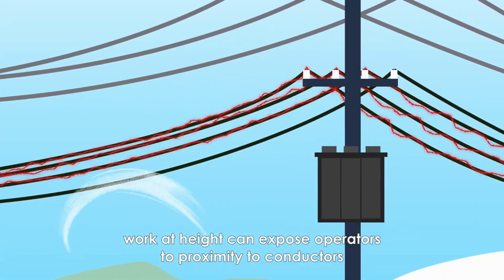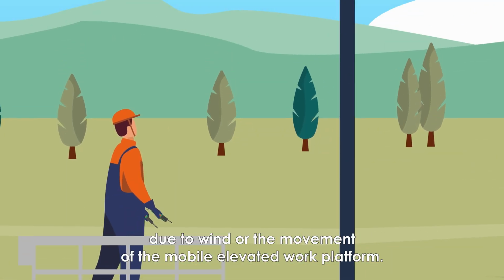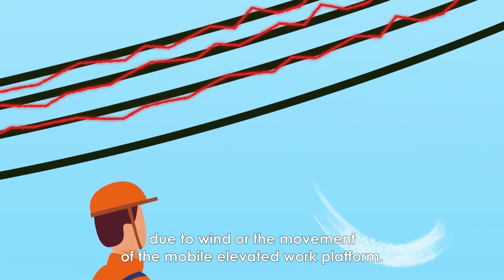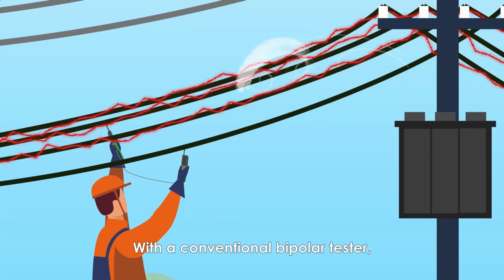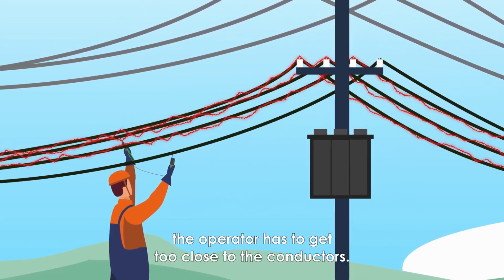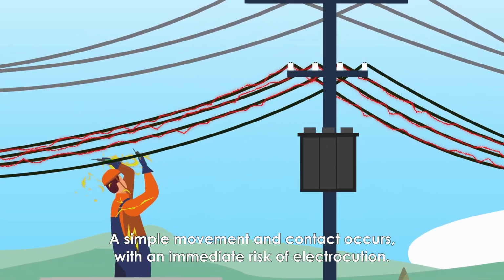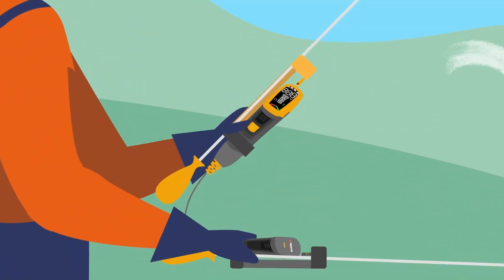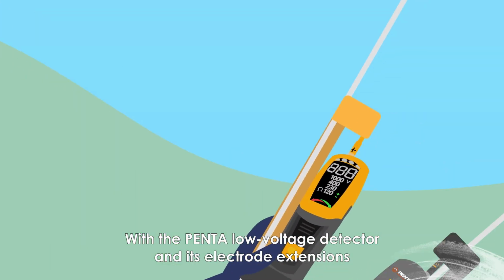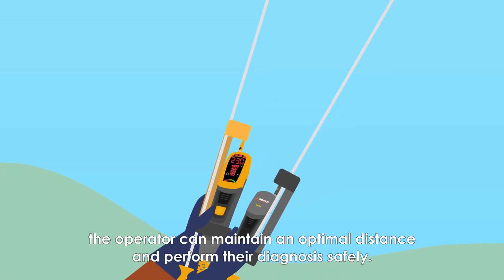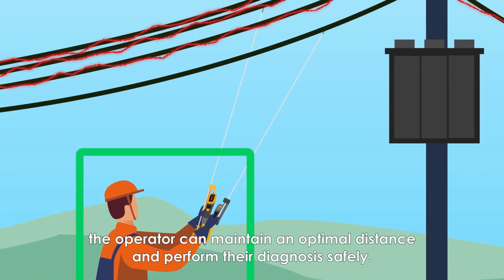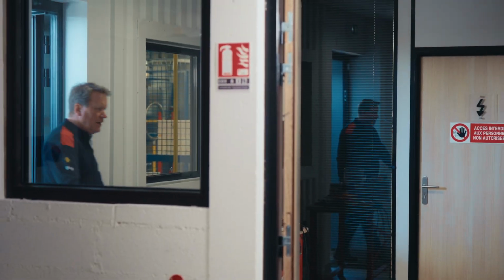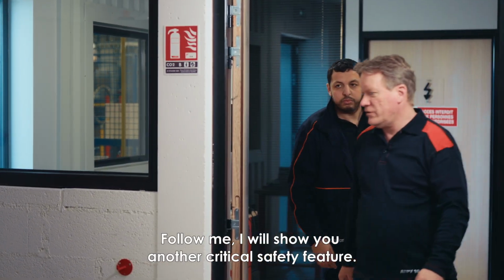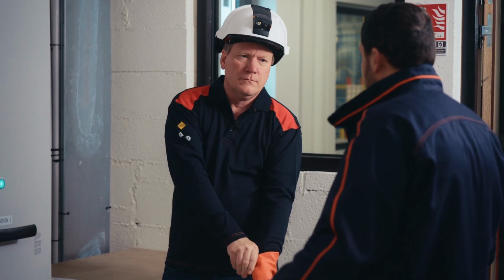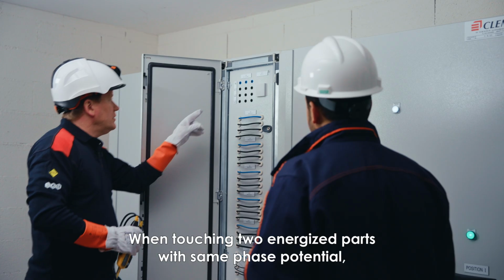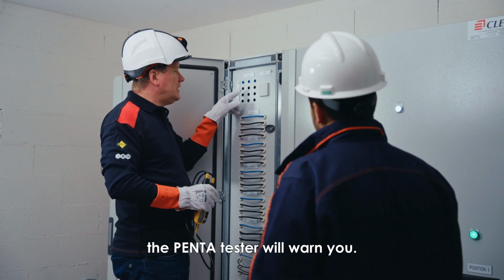In the field, work at height can expose operators to proximity to conductors due to wind or the movement of the mobile elevated work platform. With a conventional bipolar tester, the operator has to get too close to the conductors. A simple movement and contact occurs, with an immediate risk of electrocution. With the Penta low voltage detector and its electrode extensions, the operator can maintain an optimal distance and perform their diagnosis safely. Follow me. I will show you another critical safety feature. When touching two energized parts at the same potential, the Penta tester will warn you.